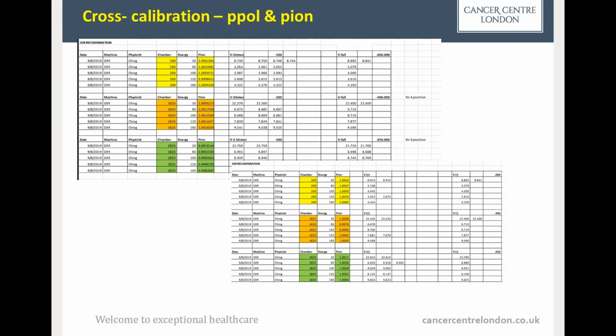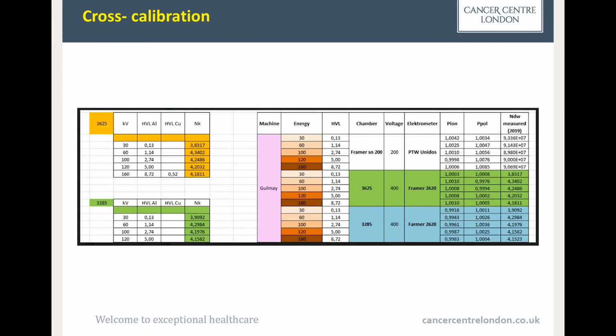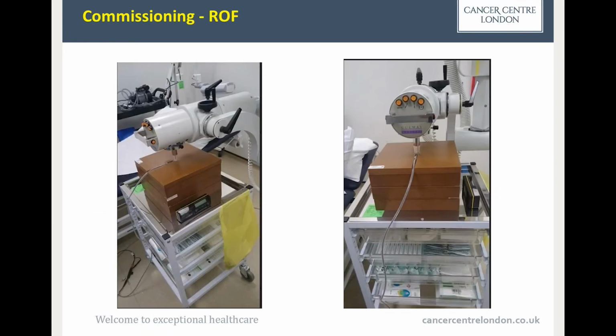Part of this intercomparison was also establishing specific calibration parameters, expressed by polarization and recombination effect. Fortunately for this energy, they are quite low and don't affect the measurements significantly. They are not very sensitive in relation to energy. Going ahead, this is the result of our cross calibration. You can see the final table, expressed by kV energy and HVL for aluminum and copper, and the calibration factor in air for our two chambers, which we use in clinical practice.